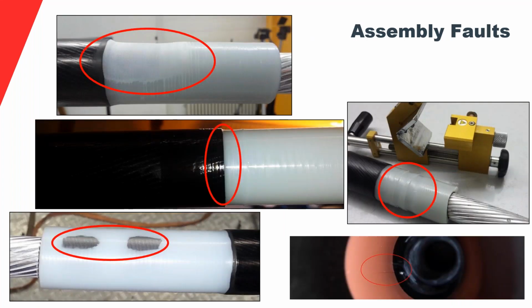Then, what can happen? These workmanship issues, freak stuff can happen in the field, like the craziest things. We sometimes get pictures sent by customers. On the top there you can see they sanded too much, so you will have a void. Then on the right, the peeling tool slipped off. Then in the picture in the middle, they also used an incorrect peeling tool.